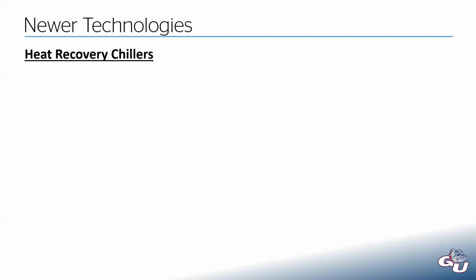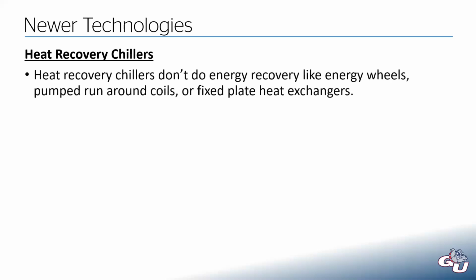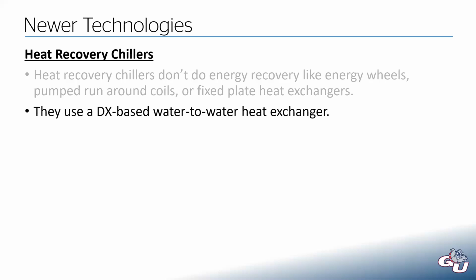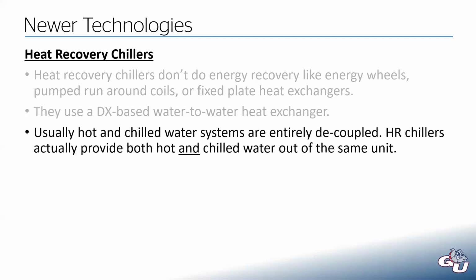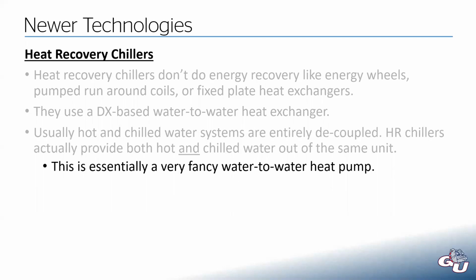The next thing is heat recovery chillers. These are not like energy wheels, pumped runaround coils, or fixed plate heat exchangers, which we just talked about when we were talking about energy recovery methods. These are using a DX based, so this is a refrigeration process, water to water heat exchanger. Normally, if you have hot and chilled water systems, they're entirely decoupled, which means they're completely separate. They don't interact at all. The chilled water system does not care what's going on with the hot water system and vice versa. But heat recovery chillers provide hot and chilled water out of the same unit. So this is essentially a really fancy water to water heat pump.